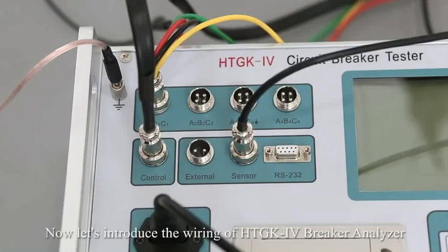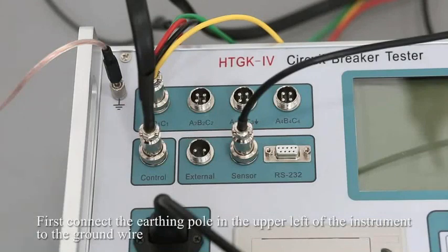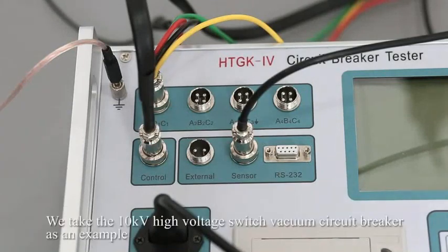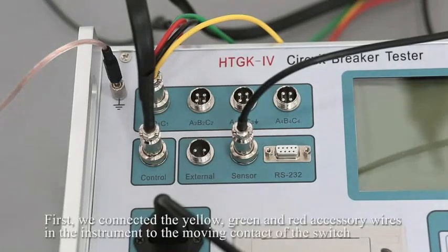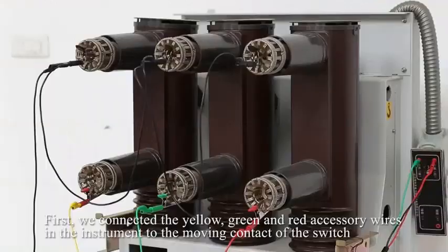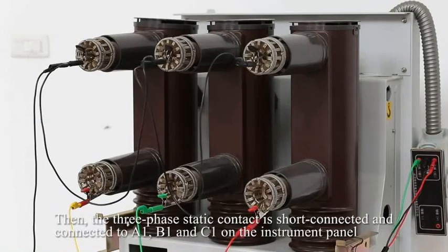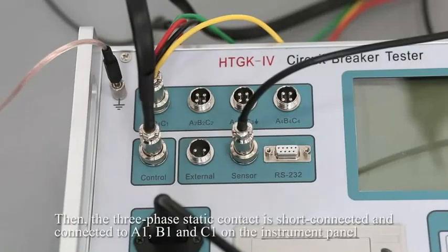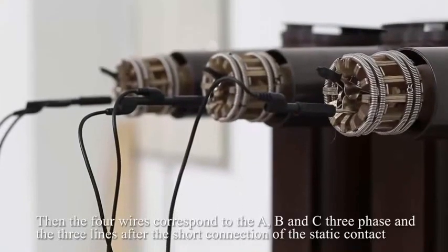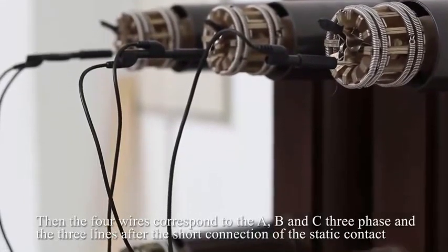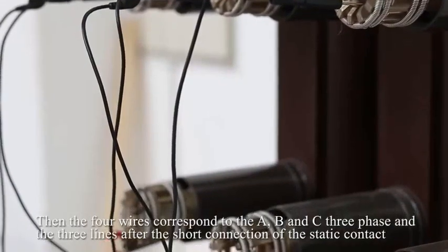Now let's introduce the wiring of the HTGK IV breaker analyzer. First, connect the earth pole in the upper left of the instrument to the ground wire. We take the 10 kV high voltage switch vacuum circuit breaker as an example. First, we connect the yellow, green, and red accessory wires in the instrument to the moving contact of the switch. Then the three-phase static contact is short connected and connected to A1, B1, and C1 on the instrument panel. Then the four wires correspond to the A, B, and C three-phase and the three lines after the short connection of the static contact.